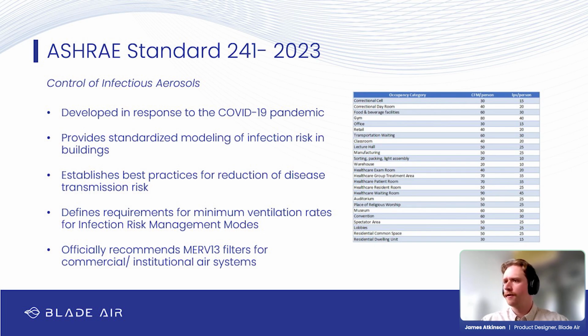What happens? It also defines a new operating mode called infection risk management mode. So if we were to have a new pandemic, and let's hope we don't, there's a new operating mode in your air handling system to account for that. So if you need to have people indoors, but there's an ongoing risk, you can increase ventilation rates, increase air cleaning and filtration to really keep everyone and all your building occupants safe. It also officially recommends MERV 13 for commercial air systems. So a lot of people have been changing to MERV 13 and finding that now all of a sudden their system doesn't work because you have this really high efficiency filter, but it's also blocking a lot of air.